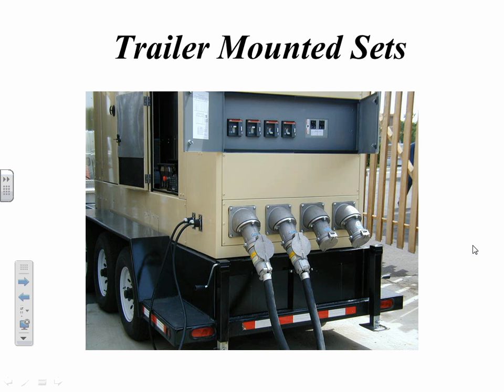But what it was actually showing was, in either configuration, it was 480 or 240 for this particular setup of the bars that they had on this unit. So it was actually a 277/480 set, which is much more common. I didn't know that until we got back to the office. Studied that diagram. And I've only seen 240/480 three phases in my career. That tells you how common they are.